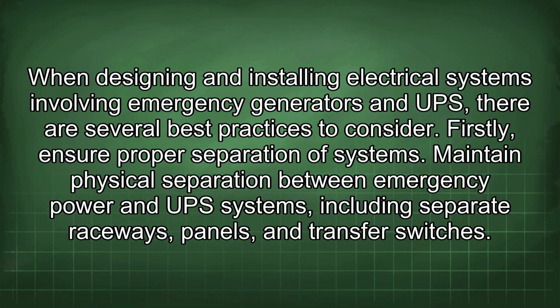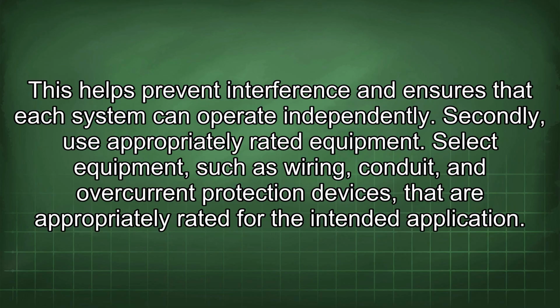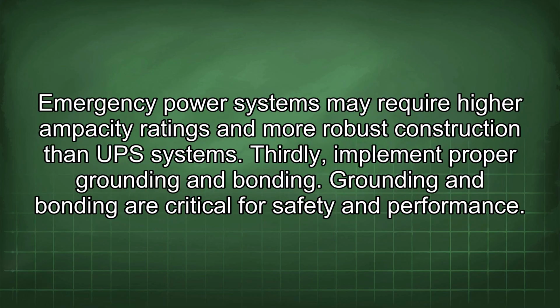Firstly, ensure proper separation of systems. Maintain physical separation between emergency power and UPS systems, including separate raceways, panels, and transfer switches. This helps prevent interference and ensures that each system can operate independently. Secondly, use appropriately rated equipment. Select equipment such as wiring, conduit, and overcurrent protection devices that are appropriately rated for the intended application. Emergency power systems may require higher ampacity ratings and more robust construction than UPS systems.